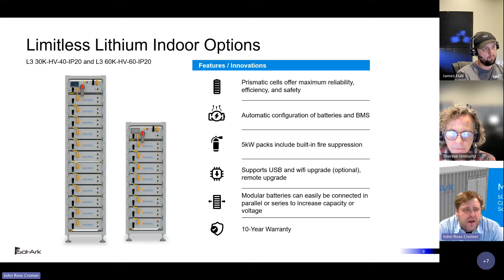We got some indoor and outdoor battery options. One nice thing about these batteries is they're made for Sol-Ark inverters. So there's very little to do in terms of wiring and commissioning. The indoor batteries you assemble yourself, but the assembly is very straightforward. The outdoor batteries come pre-assembled in terms of the battery modules and racking. The battery modules have built-in fire suppression. So NFPA 855 allows for the jurisdiction to utilize alternative means of fire suppression, including aerosol-based fire suppression built into the battery module. So your fire suppression is included: lithium iron phosphate chemistry, prismatic cells. The batteries have a 10-year warranty on them.